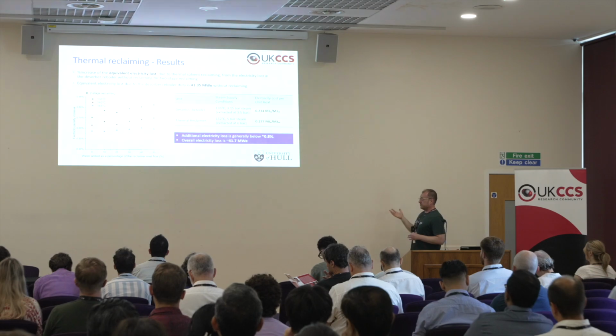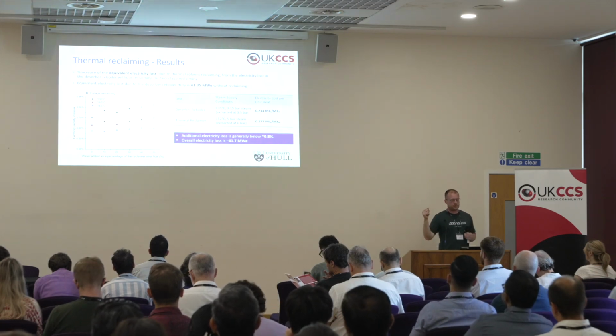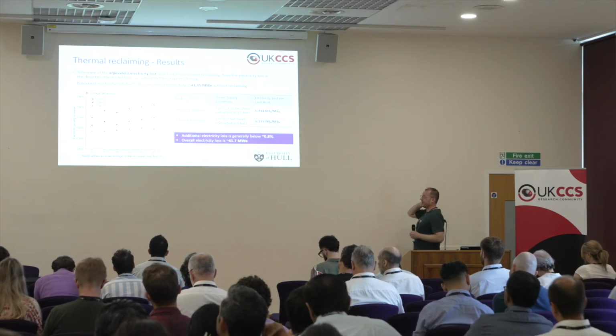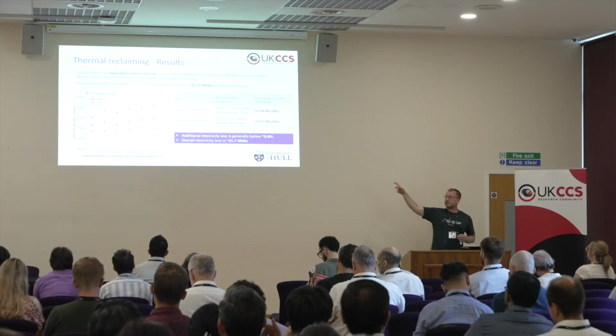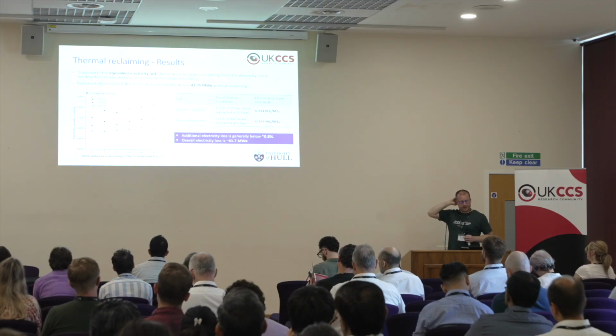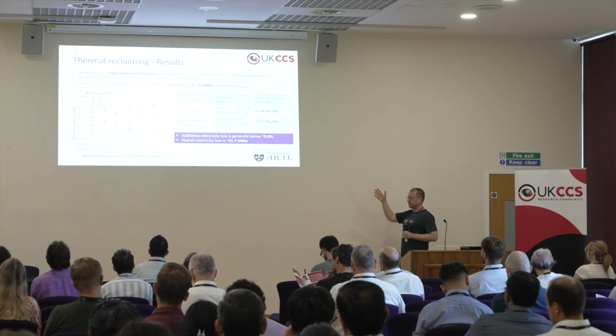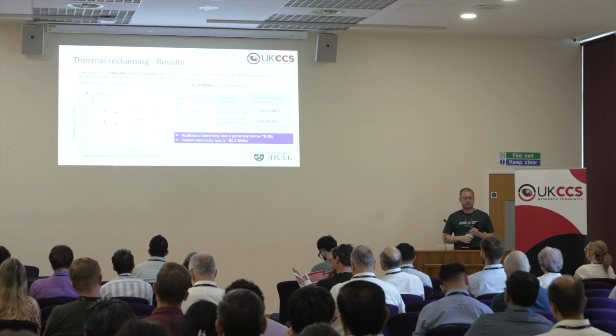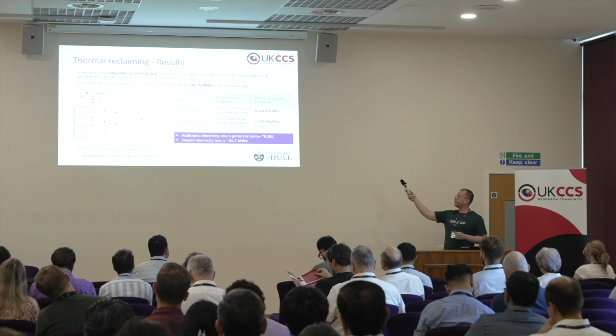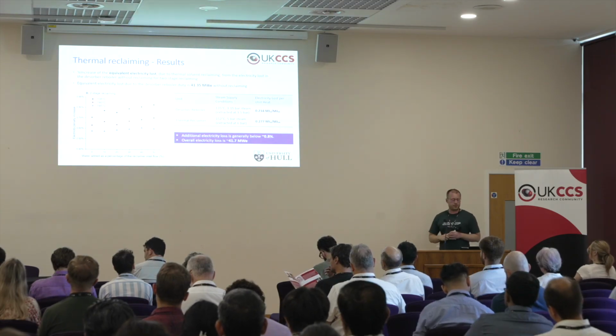Now, about the additional penalty of reclaiming. We said through this configuration we can recover most of this energy. We present that here in terms of the equivalent electricity lost. Now, without reclaiming operation, this equals 41.35 megawatts. Because the reclaimer operates at higher pressure, we need to extract a higher quality steam. For the desorber reboiler, 135 degrees, 3.15 bar, while for the thermal reboiler, 152 degrees, 5 bar, which obviously leads to different energy conversion factors. The bottom line is that the additional electricity loss is generally very low, around 0.8%. So the overall electricity loss from 41.35 goes up to 41.7.